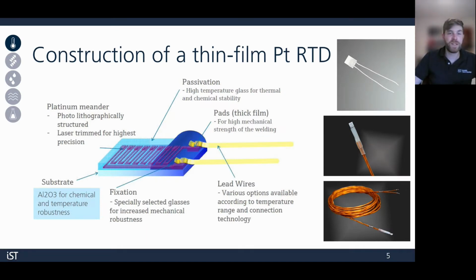So let's go more in depth about resistance temperature detectors, or RTDs. So for thin films, here's what they generally look like. We start with an aluminum oxide substrate, then we sputter a thin metallic layer on the top side. This is usually platinum or nickel. Then using spin coating, photolithography, and etching, we shape the meander structure, which will act as the temperature sensitive resistor. The meander is then laser trimmed to the customer specified nominal resistance. Then a thick film glass passivation paste is applied over the top. Finally, the wires are welded using a resistance weld on each pad, and another paste is applied and hardened to protect the wire weld area.